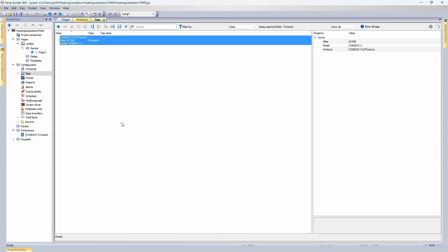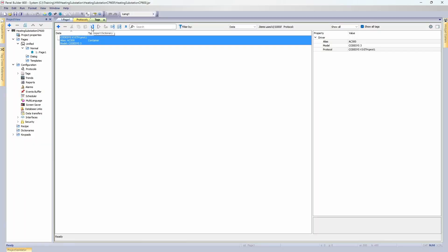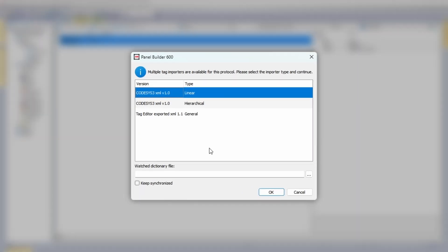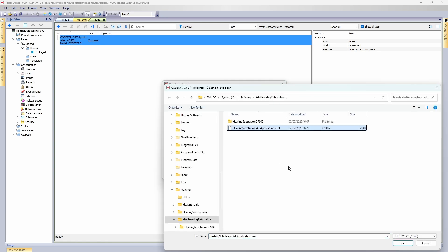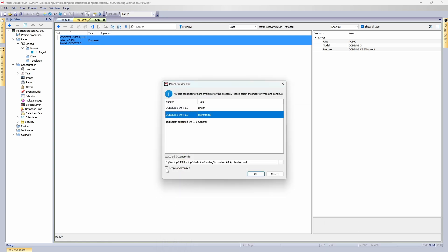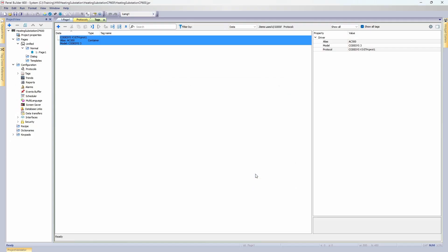Tags is just another name for variables used inside the HMI project. You can see that the protocol driver is already there, but there is nothing under it. Select the driver you want to add tags to, click Import, and select Hierarchical Type — this way tags will stay grouped by lists. Select the Symbol Configuration XML file, and tick the Keep Synchronize checkbox. This way, whenever you have changes to the XML file, they'll be automatically populated here in the tags configuration. After you hit OK, all the tags defined in the Symbol Configuration file will be added.